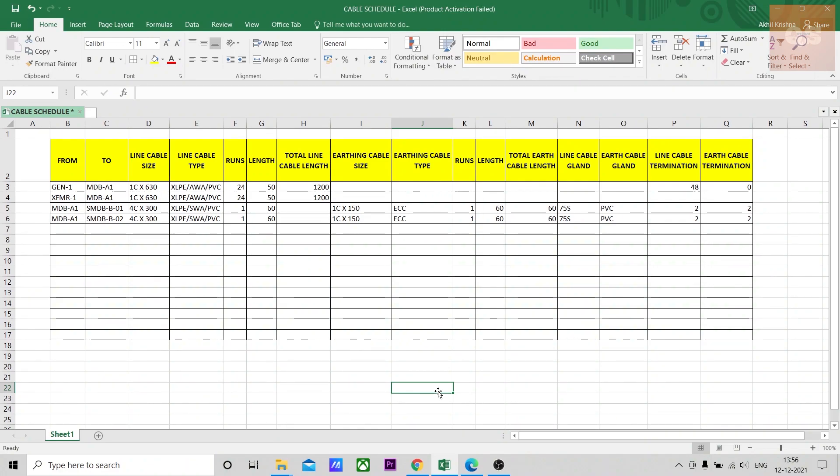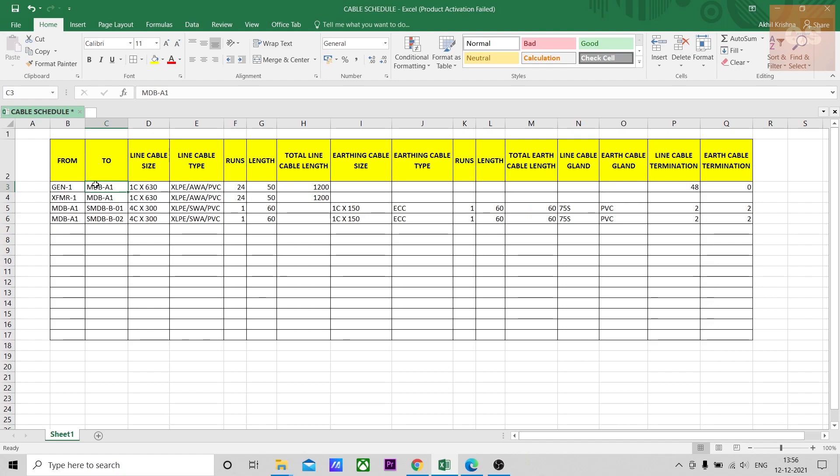Depending upon the type of cable, the type of gland can also be obtained using this chart that is easily available from the net. Termination is basically, you know, there is a from and to, mainly it is called outgoing and the incoming. For one cable there will be two terminations. So here the calculation that I have done is F3 into 2, so F3 is the runs.